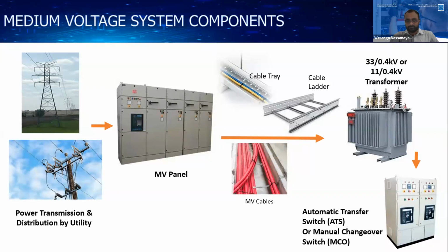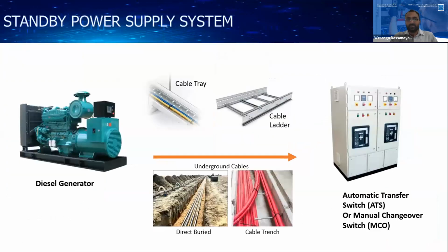So when you are installing a distribution system, it is required to calculate whether the cables used are adequate to carry the current in the system. So this is what we have to inspect in a medium voltage system. Next we will go to a standby power supply system, which is mostly fed by a diesel generator.